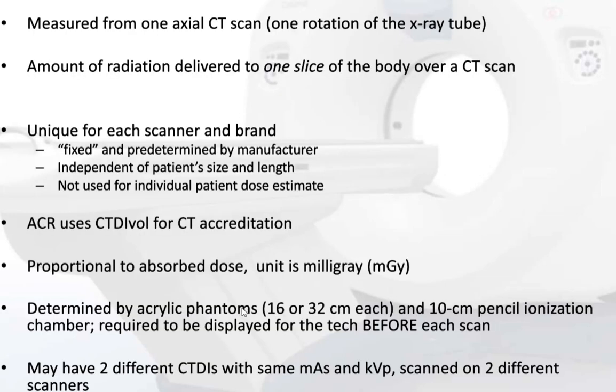The CTDI or CT dose index has several variants — there is weighted and volume. CTDI volume is measured from one axial CT scan, one rotation of the X-ray tube. It is the amount of radiation delivered to one slice of the body over a CT scan. It is unique for each scanner and brand, fixed and predetermined by the manufacturer, independent of patient size and length.